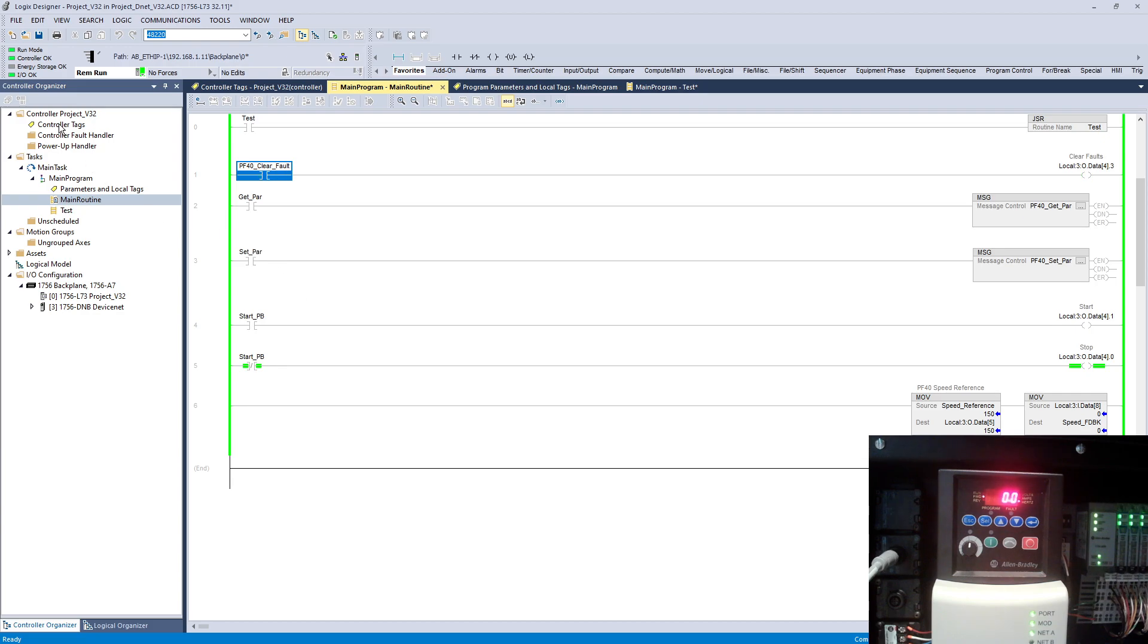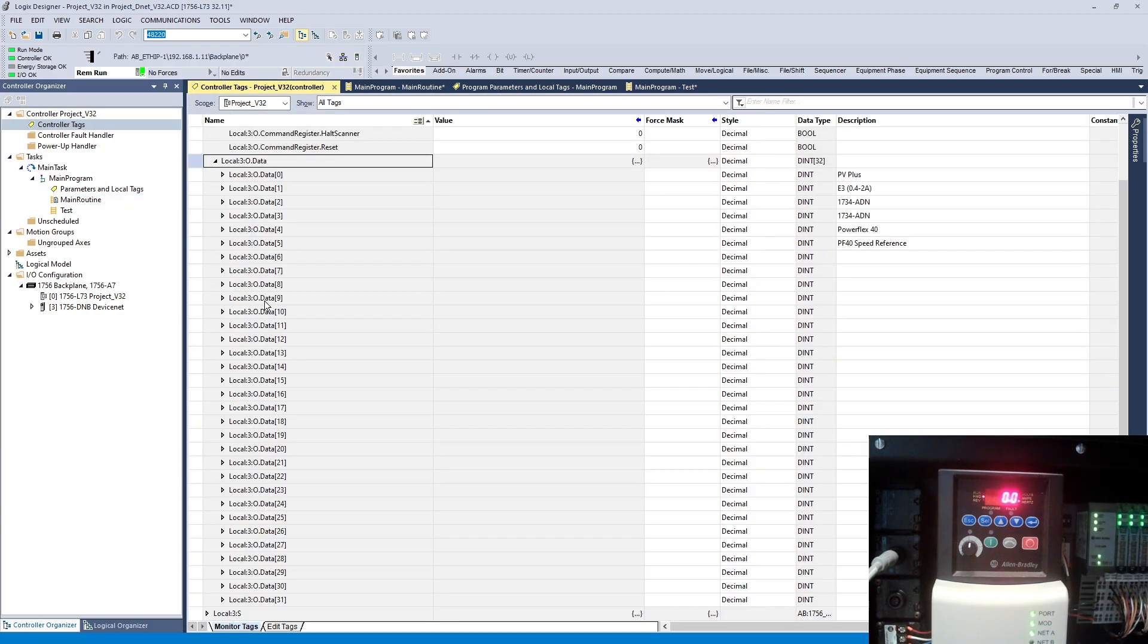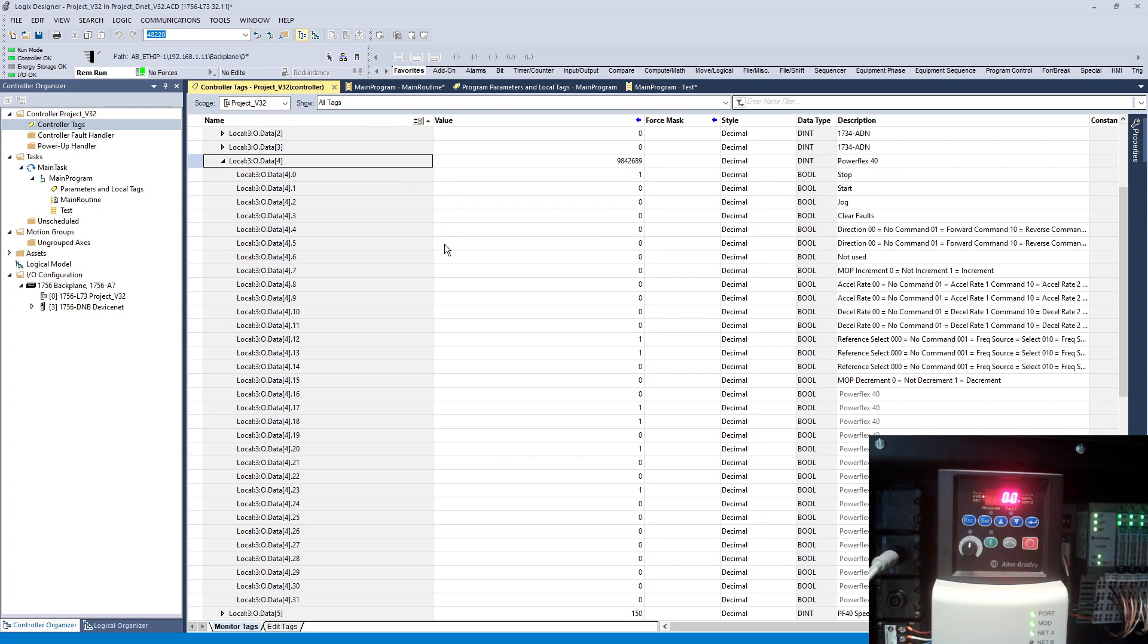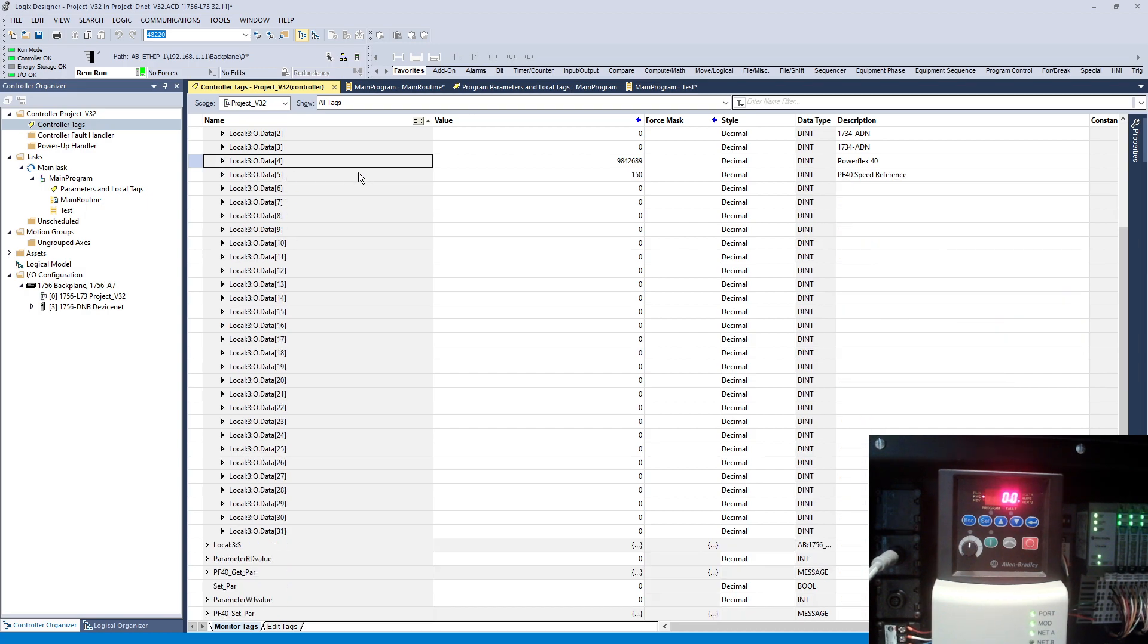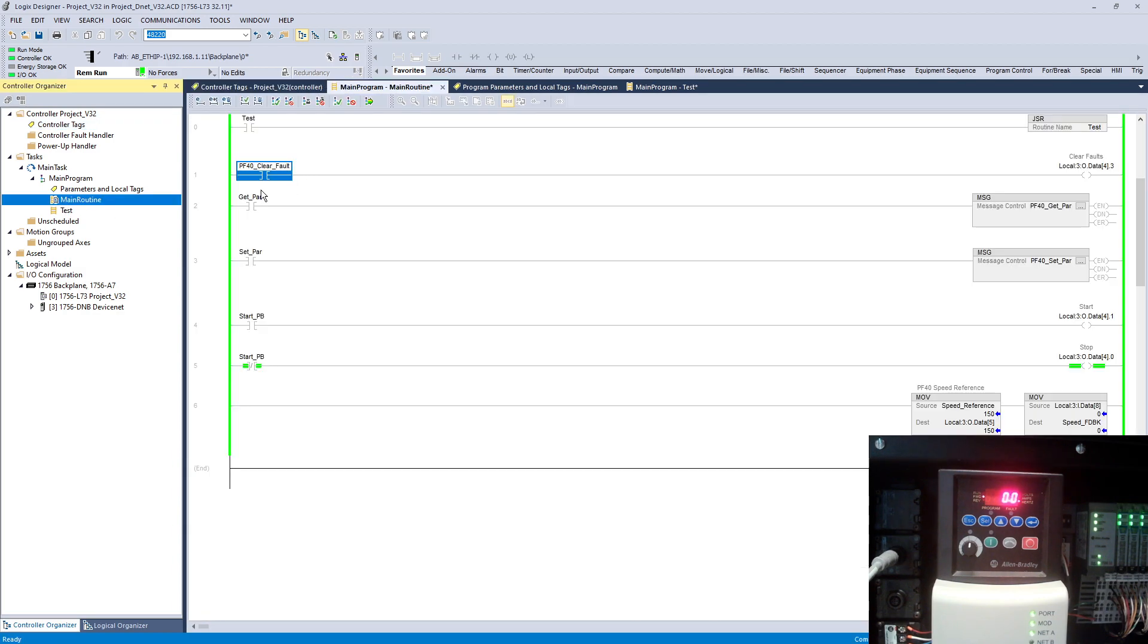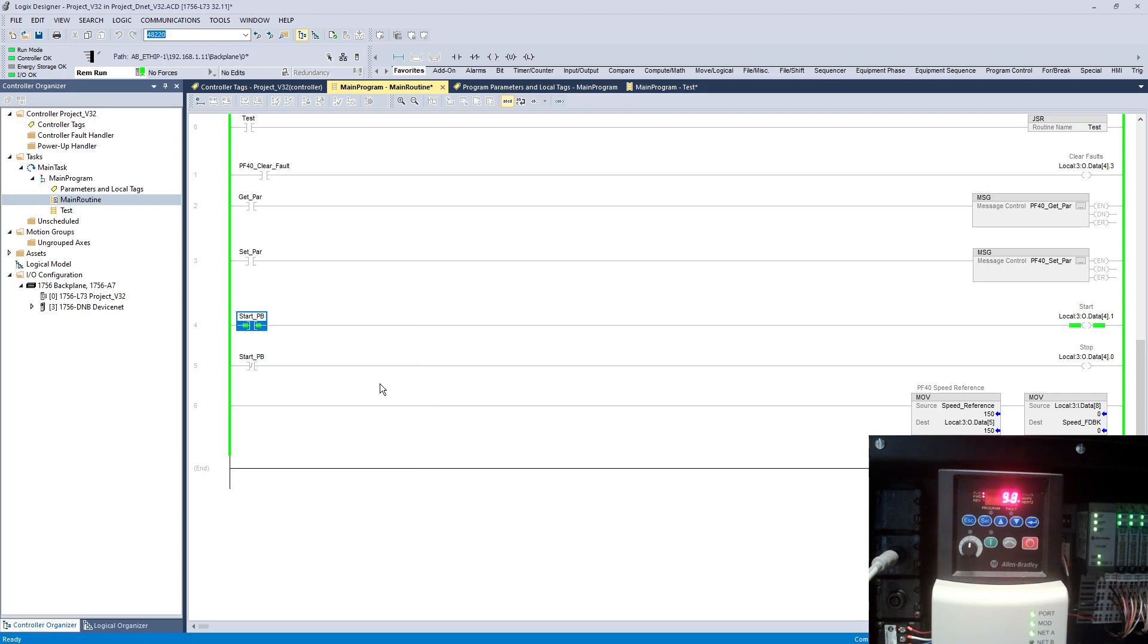So now I'm using on number 4 all 32 bits over here. Now my speed reference is not coming on the input side from the other location or going from here. If I start my VFD it will not go anywhere.